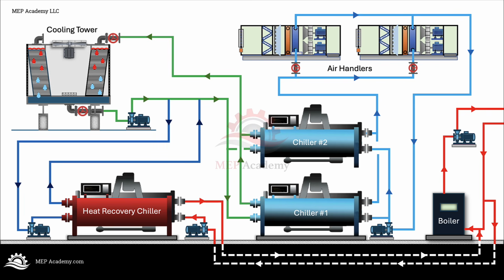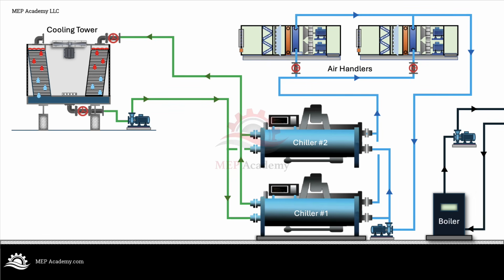To understand how this works, let's first look at a normal water-cooled chiller. In a typical chilled water system, chilled water leaves the evaporator side of the chiller and flows out to air handling units, fan coils, process equipment, or other cooling loads. As the chilled water moves through the building, it absorbs heat. The water returns warmer to the chiller.